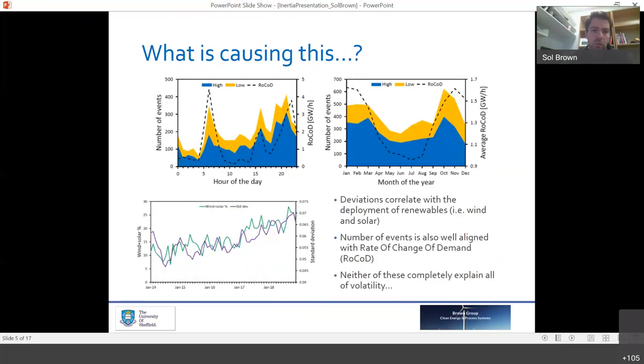So here we've plotted the number of events against the RoCoD, so the rate of change of demand. We look for a correlation against the amount of wind and solar, so renewables, deployed on the grid, and there is a correlation, but it's not sufficiently large for it to be causative. So the deployment of renewables in itself is not causing greater amounts of volatility in frequency. But you can also see from the two graphs at the top that the number of events, both high and low, are very well aligned with the rate of change of demand.